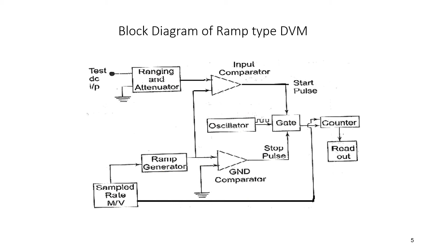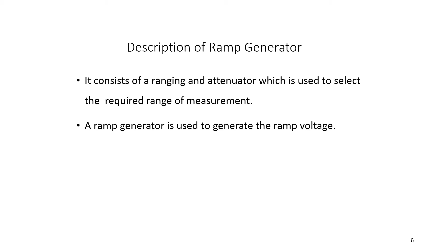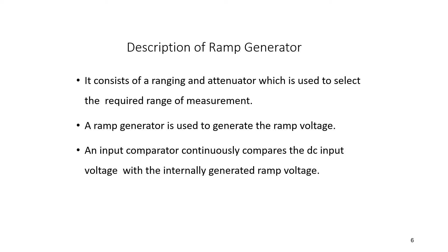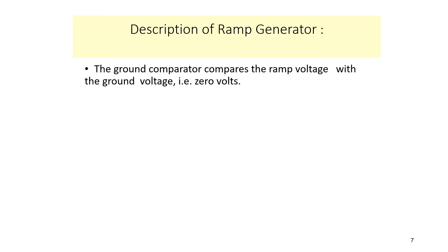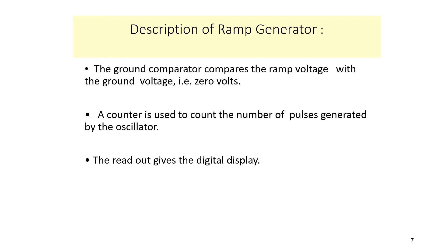So as I told you, it consists of a ranging attenuator which is used to select the required range of measurement, a ramp generator which is used to generate the ramp voltage, an input comparator which continuously compares the DC input voltage with the internally generated ramp voltage, and the ground comparator which compares the ramp voltage with the ground voltage, that is 0 volts. A counter is used to count the number of pulses generated by the oscillator. The readout gives the digital display.